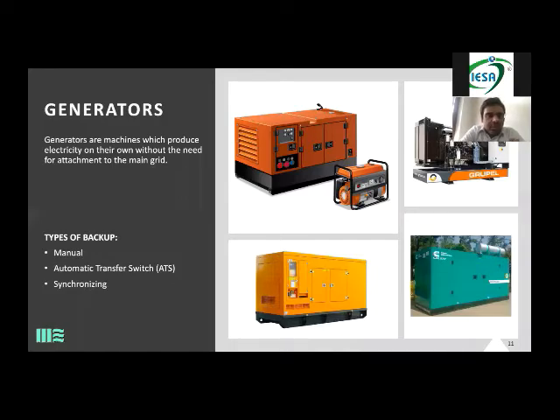So if we have 12 gensets on site to cater to your load, in synchronization you have two more extra. So if your load is 4,000, make it 5,000 kilowatts, because anyways you make up backups. In synchronization, all the 12 gensets are running on load. Nothing is running idle, nothing is backup. So they are backup of each other. If something happens to one, the other takes up. So then you're creating 12 backups on site.